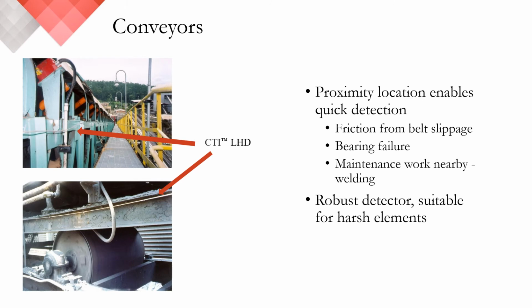Another common application within the power gen market is conveyors. In a coal-fired power plant, conveyors are used extensively. Some of the common issues seen here are bearing failures and belt slippage, both of which could cause overheating and potential sparking in the presence of coal dust. Designated as a classified hazard, the potential for fire is obviously much greater. Again, we're looking at proximity detection because we want to be as close as possible to these areas to detect and react as quickly as possible.